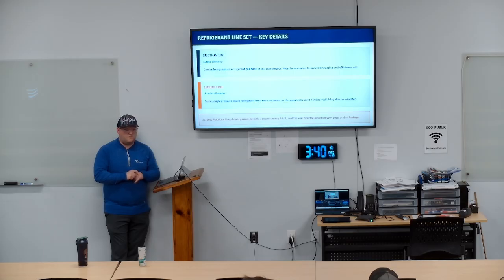It varies based off of what type of equipment. So if it's a bigger, say it's a vertical air handler inside, bigger outdoor unit, we might have to up the thickness of the insulation wall. So that's why we're not always getting 1/2 inch insulation. Sometimes we get 3/4 inch or 1 inch. That's what it has to be on that equipment.